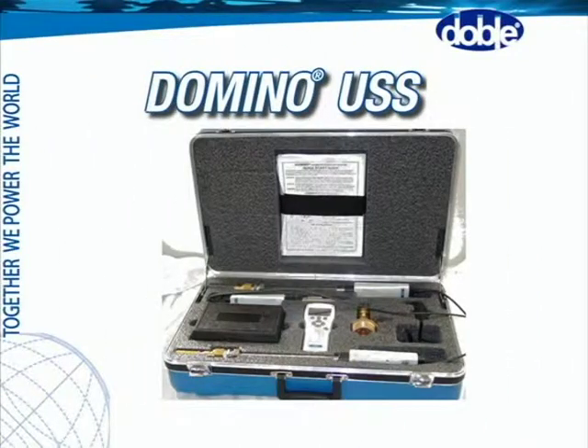The first thing we should discuss is the actual Doble case that the Domino USS is housed in. As you can see, it's a hard molded case that resists many impacts. In addition, it has oil resistant foam that's part of the case itself. The indicator is housed in this hole here. The toolbox is housed over here, and the oil probe that belongs to the moisture and oil sensor belongs here. These two pockets are actually empty for the basic kits, but as you can see, they're expandable to hold more oil probes or a dew point probe if necessary. Here we have a pocket for the instruction manual, and here we have the oil sampling manifold. Over in this corner we have the AC adapter with the plug.